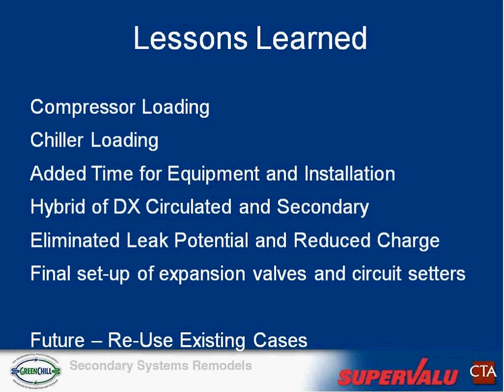compressors. They were looking at the supply water temperature, and basically they made the controller think it was trying to match a load, a pressure they were trying to maintain. At first things weren't working. There was a lot of cycling of compressors and even of solenoid valves, so they went back, got the superheats figured out, and that settled down the compressor cycling, and the superheats beyond the expansion valves there on the chillers.